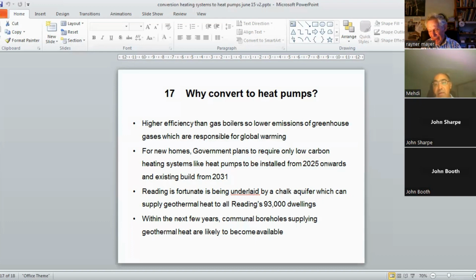And the problem of the lack of supply was still there, regardless of whether it's air source or ground source. There is a lot of research and development in that area to provide demand response. And the main challenge, I can to some extent understand, is the limitation of the energy suppliers. They are committed to reducing the peak demand, because the peak demand is sometimes 3 to 4 times the off-peak energy demand. They want to reduce the peak demand that dictates how much they can supply. And heat pump technology, generally speaking, operates at maximum capacity during the peak hours, and this is their problem.